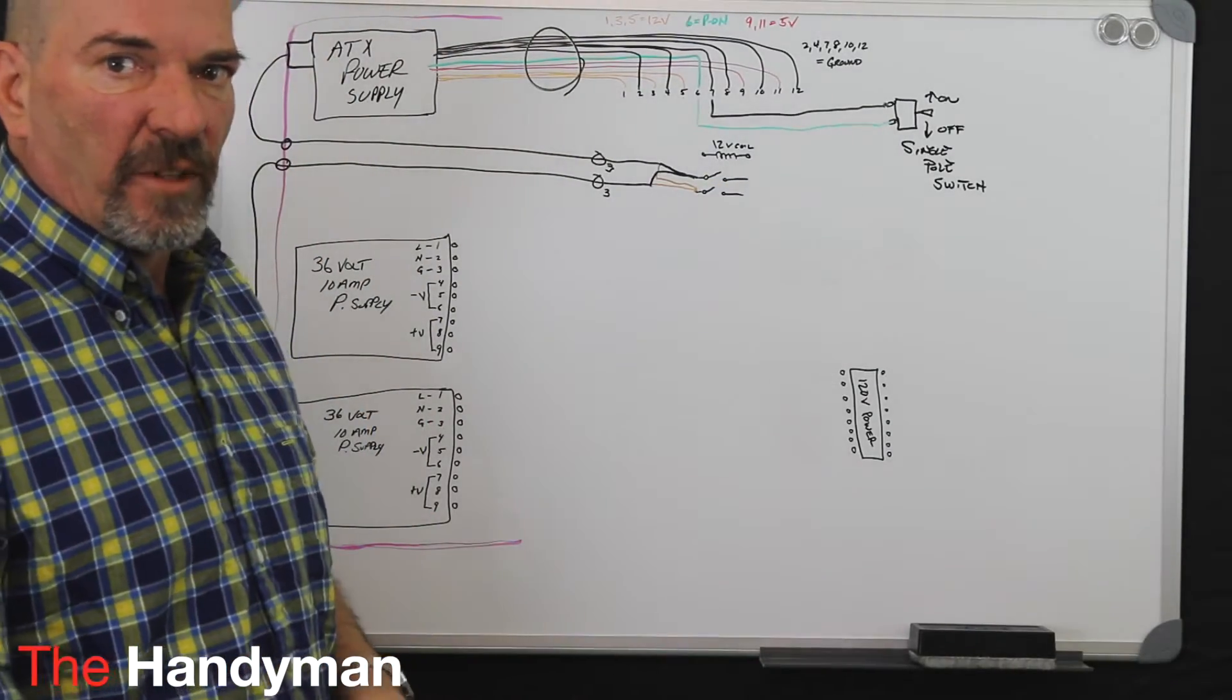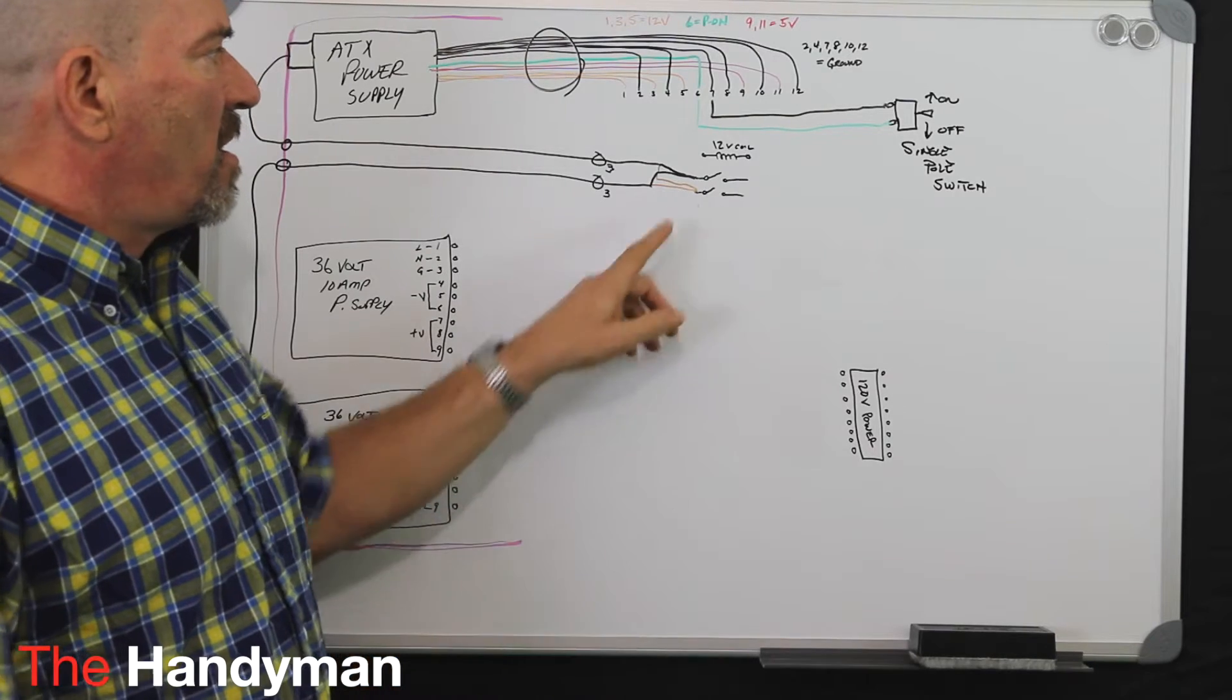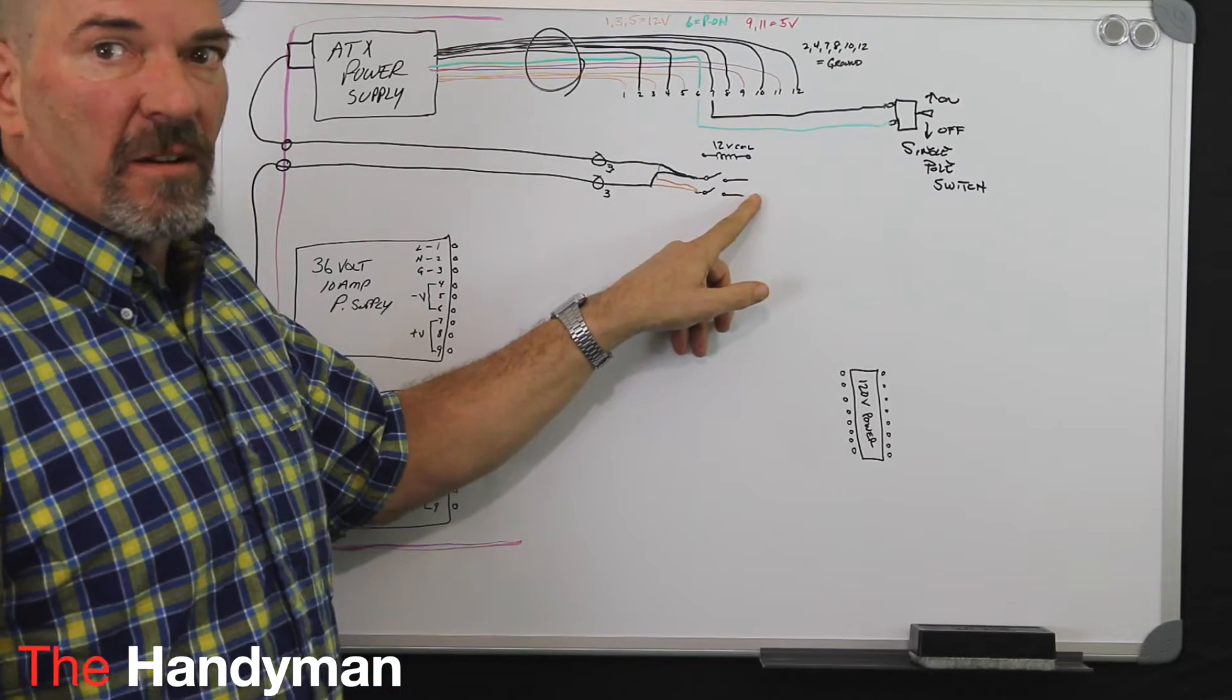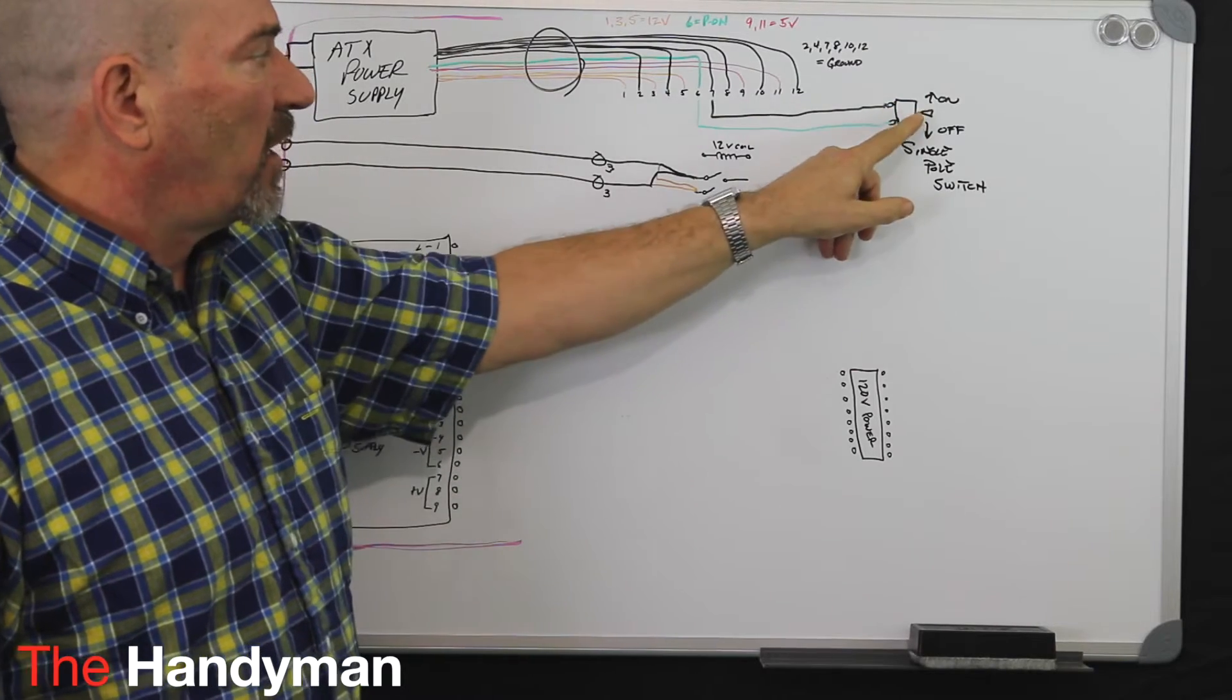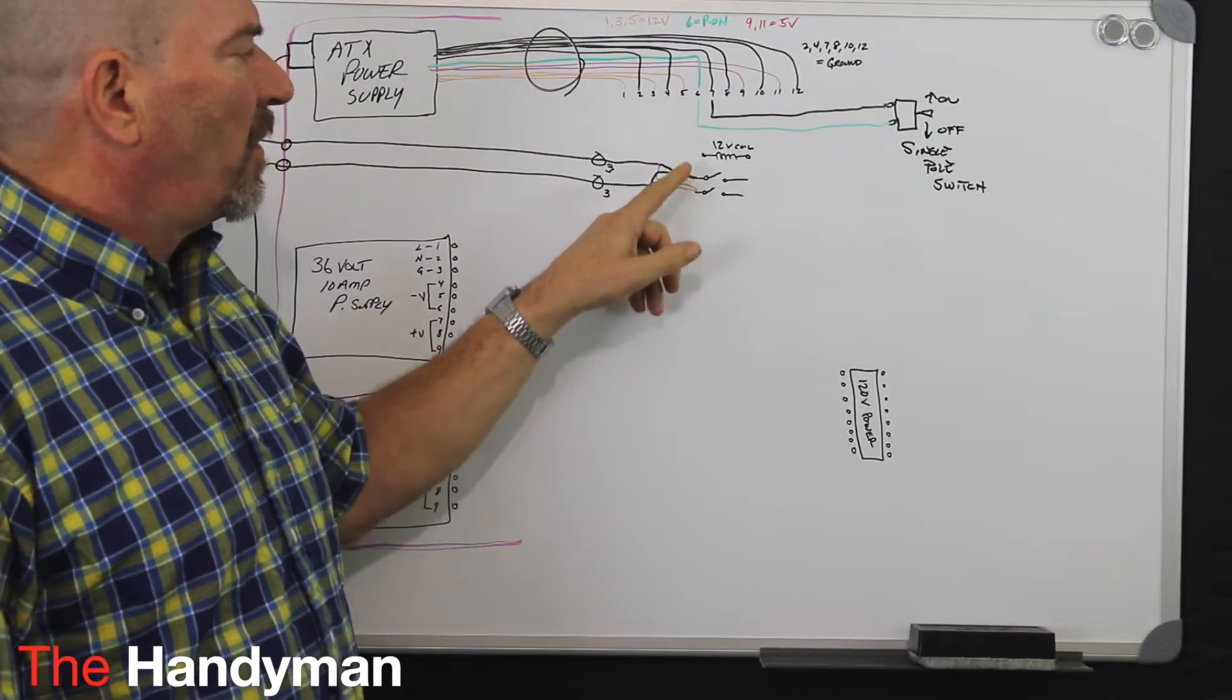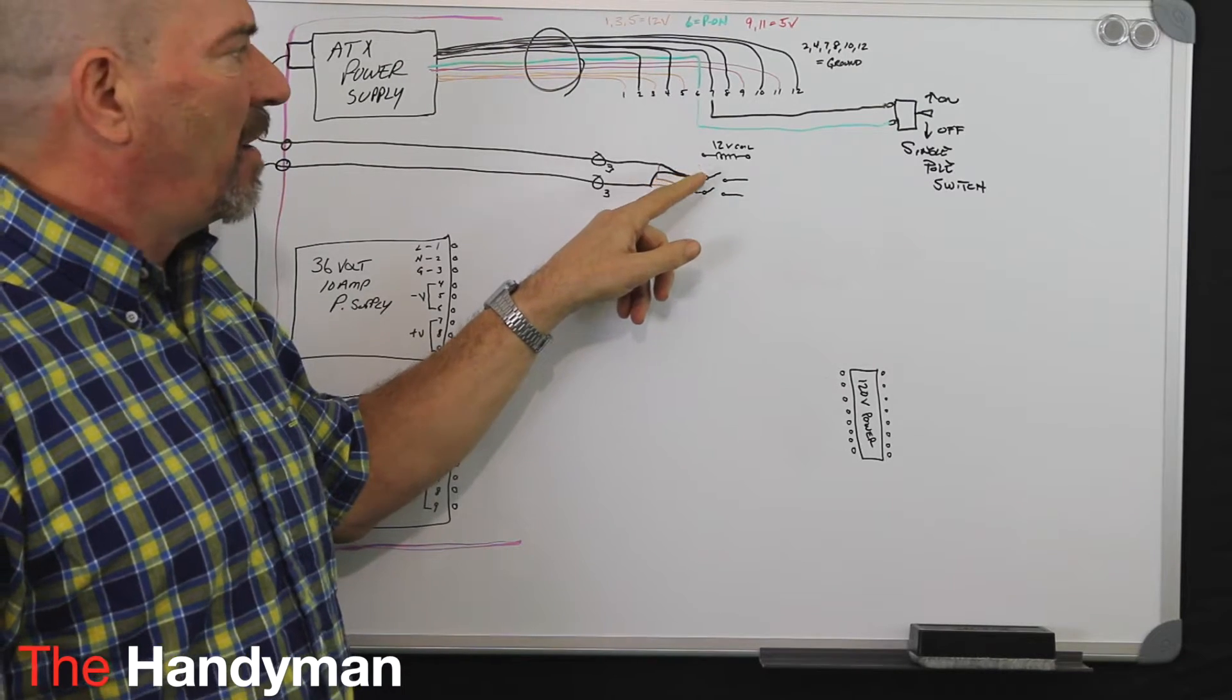Now don't get these contacts confused. You do not want to run the white on one side of the normally open and the black on the other. That's not good because when you fire up this switch, bang, that's a dead short. They need to go to one side and parallel them under each terminal screw.